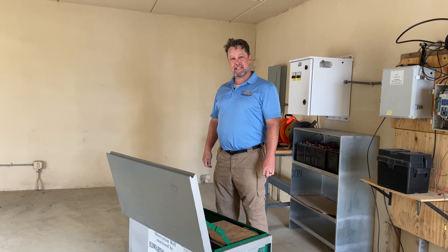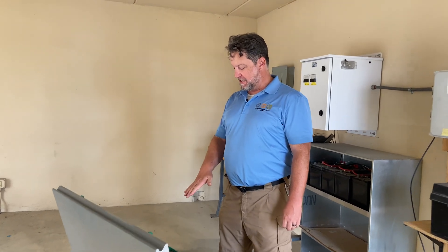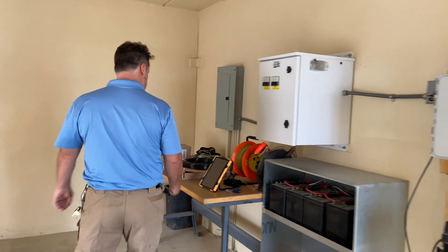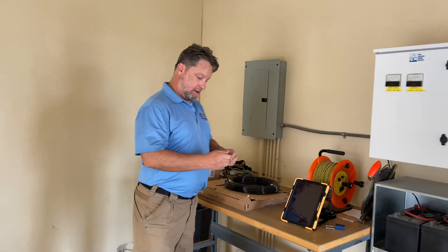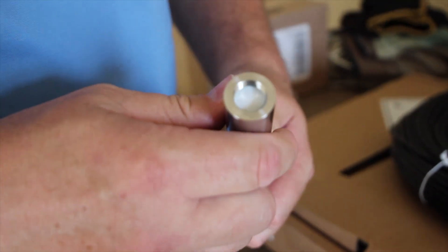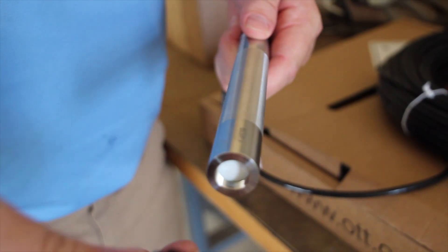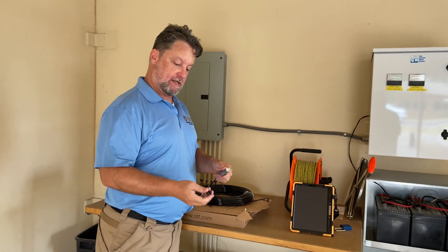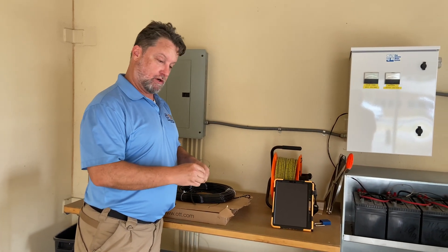The water level at J17 is measured with three different instrumentations here — three pressure transducers. The pressure transducer has a sensor on the end and is measured by the amount of pressure or force that is applied upon the sensor. Then it is converted into an engineering unit, in this case being the amount of feet below water level.